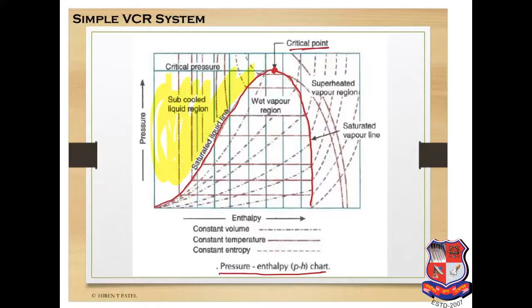Up to the critical point, the line is known as the saturated liquid line, and after the critical point, the line is known as the saturated vapor line. This is the most convenient chart for studying the behavior of the refrigerant. The saturated liquid line and the saturated vapor line merge into a point that is known as the critical point. A saturated liquid line is one which has temperature equal to the saturation temperature corresponding to its pressure, and the space to the left of this saturated liquid line, this area, is known as the subcooled liquid region. The space between this liquid line and vapor line is called the wet vapor region, and the right hand side of this saturated vapor line is known as the superheated vapor region.